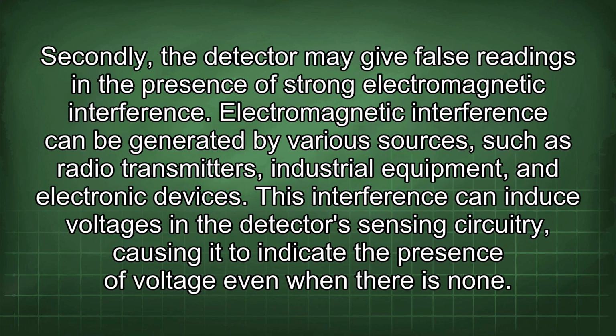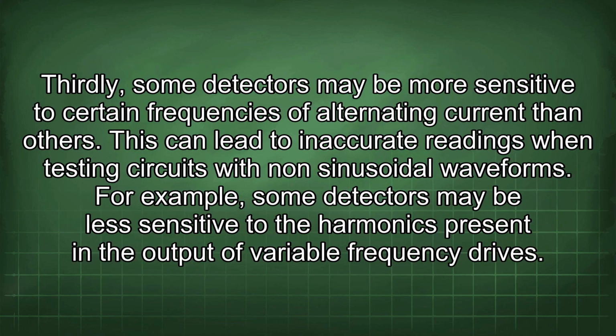Secondly, the detector may give false readings in the presence of strong electromagnetic interference. Electromagnetic interference can be generated by various sources such as radio transmitters, industrial equipment, and electronic devices. This interference can induce voltages in the detector sensing circuitry, causing it to indicate the presence of voltage even when there is none. Thirdly, some detectors may be more sensitive to certain frequencies of alternating current than others. This can lead to inaccurate readings when testing circuits with non-sinusoidal waveforms. For example, some detectors may be less sensitive to the harmonics present in the output of variable frequency drives.